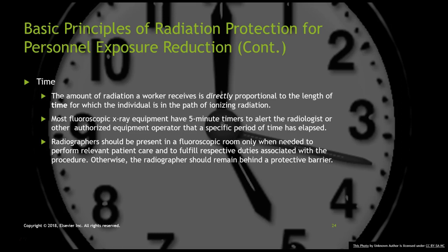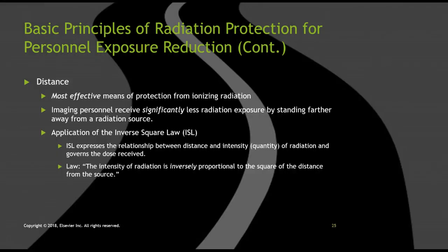So just to get a little bit more into the time, the amount of radiation a worker receives is directly proportional to the length of time that you are near the path of ionizing radiation. Most fluoro X-ray equipment have a 5-minute timer to alert the radiologist or other equipment operator. Radiographers should be present in the fluoro room only when needed to perform a relevant patient care or duty associated with the procedure. Otherwise, stand back behind a protective barrier, behind the radiologist, wherever you need to be. Distance, the most effective means of protection from ionizing radiation. As you will know, it's the inverse square law. Imaging personnel receive significantly less radiation exposure by standing farther away from a radiation source.